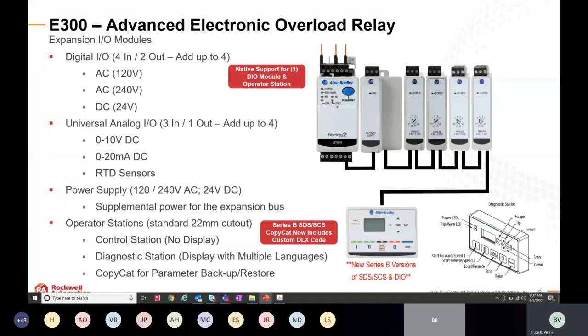So if we look a little bit closer at some of the expansion modules that are offered with the E300, again, very powerful and a very versatile offering. So you saw some of the native I/O options that the control module supports. But let's say your application requires some additional thermal monitoring or maybe some vibration monitoring, and you don't have enough I/O to do that with the E300. You can actually build out the E300 and add expansion I/O to that device and make it a kind of remote I/O rack. So instead of having to add additional components like remote I/O, you can add this to the E300 instead and bring all that information in through the E300 and have access to it through that web browser or through your PLC system as well. So something to keep in mind there. That's very, very powerful for the E300.